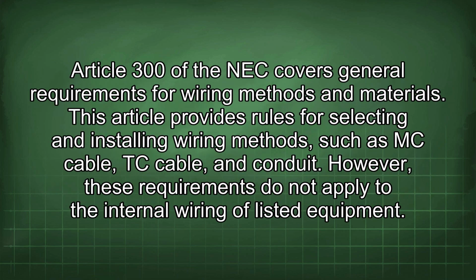Article 300 of the NEC covers general requirements for wiring methods and materials. This article provides rules for selecting and installing wiring methods such as MC cable, TC cable, and conduit. However, these requirements do not apply to the internal wiring of listed equipment.